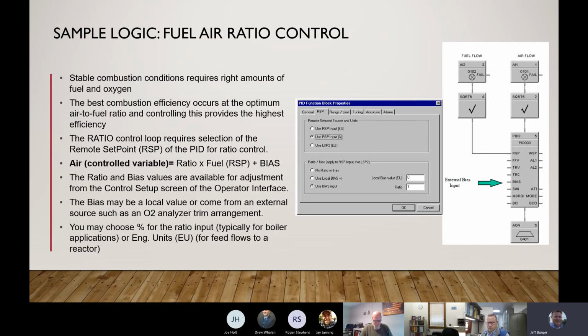Fuel-air ratio control. This is one that we do quite a bit for combustion systems. What this does is it gives you the best combustion efficiency at the optimum air to fuel ratio controlling, and this provides the highest level of efficiency for your burner system. And you can see over on the right-hand side a fuel flow input, and we're actually square rooting that input to give us our flow, and that's a pretty typical configuration if you just have a raw flow value coming into a control loop.